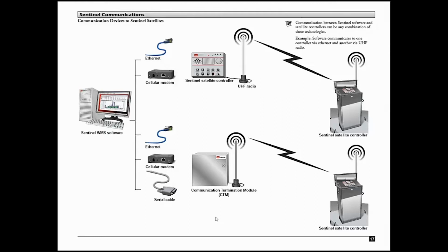Well, what's pretty cool about this technology is, let's say that I want to talk to 002. Well, if I want to talk to 2, I'm going to use the same IP address that I just plugged in to the communication tab for 001. Exact same IP address, nothing different. So when I go to communicate to 2, 3, or 4, when it reaches unit 1, it realizes that it's not the controller that I am asking to talk to or to download a change to.